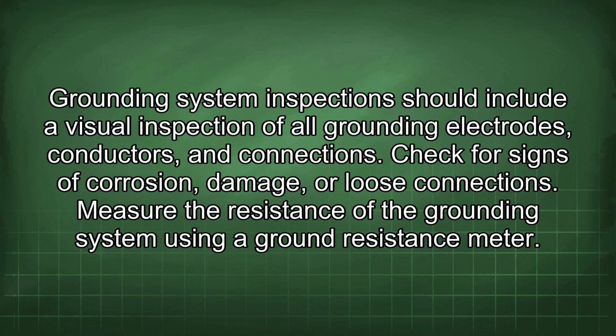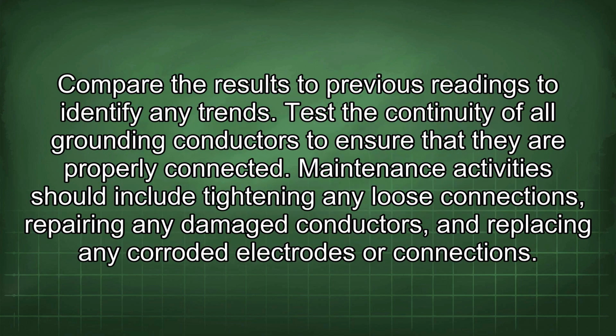Grounding system inspections should include a visual inspection of all grounding electrodes, conductors, and connections. Check for signs of corrosion, damage, or loose connections. Measure the resistance of the grounding system using a ground resistance meter. Compare the results to previous readings to identify any trends. Test the continuity of all grounding conductors to ensure that they are properly connected. Maintenance activity should include tightening any loose connections, repairing any damaged conductors, and replacing any corroded electrodes or connections.